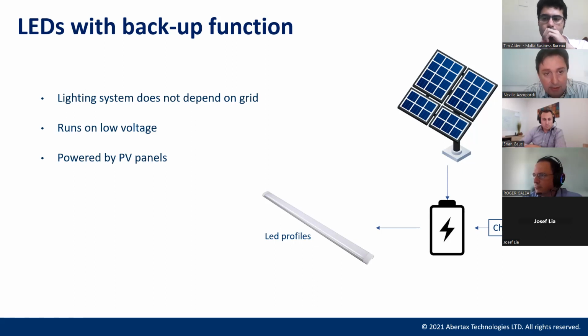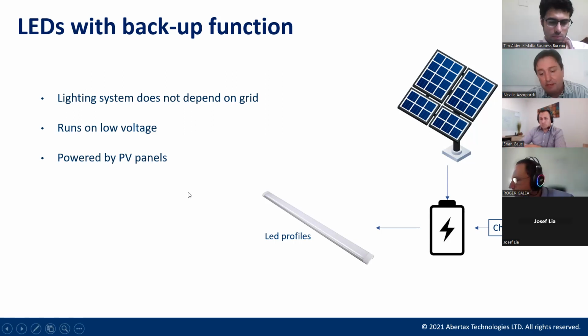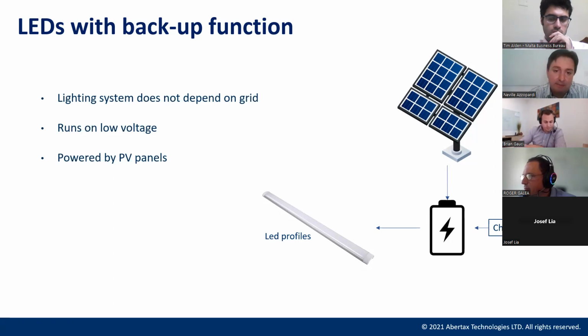This also has its advantages, and it can still be connected to the grid for backup if there is a lot of bad weather. It runs on a low voltage, so unfortunately it can only be done in small areas, but it's very reliable because we remove all the conversion power electronics, because we are working directly with low voltage from the battery to the LEDs.